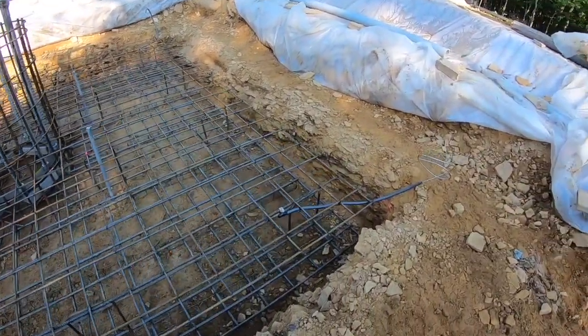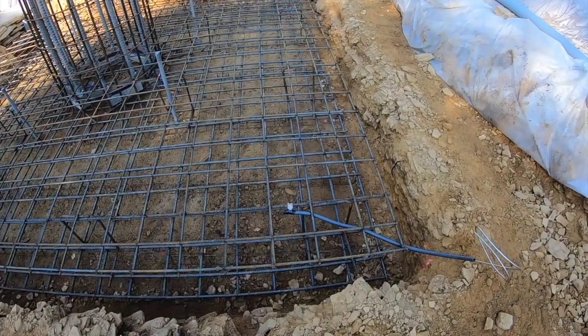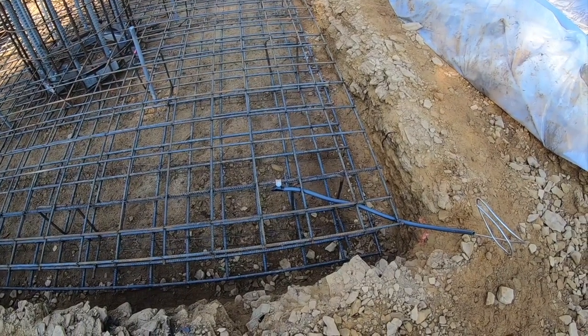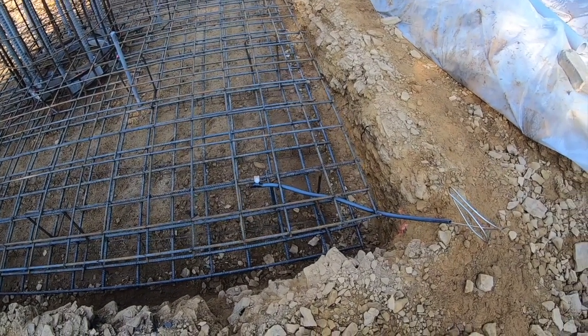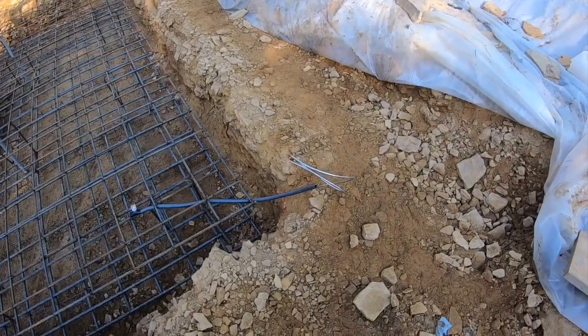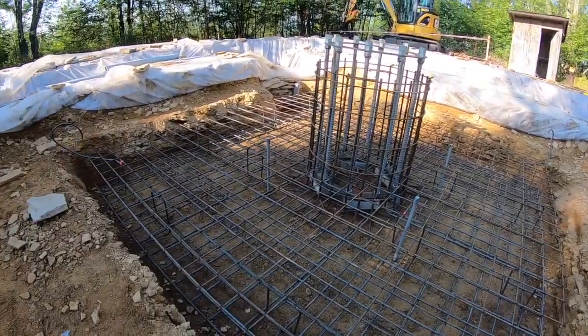And then we have our steel bonded as well with special approved rebar direct burial clips, and then we put Carflex around our number 2 tin, which is copper. It's just tin coated copper, so we got one of them on each corner.